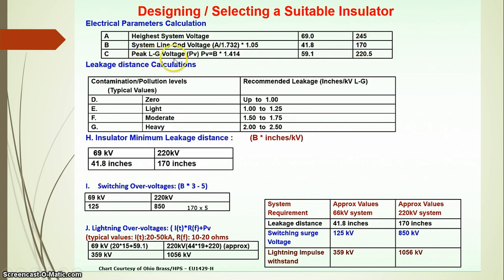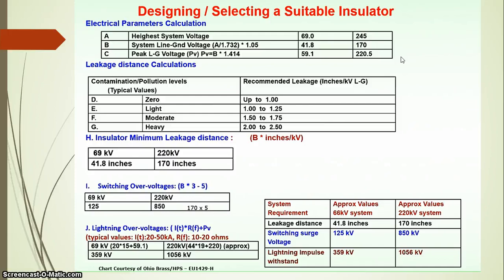The 245 kV is the maximum operating voltage level of the 220 kV system and is an RMS value, not a peak value. The peak value is calculated: 170 kV RMS line-to-ground voltage multiplied by root 2 gives a peak line-to-ground voltage of 220.5 kV. So for a 220 kV system with maximum operating voltage of 245 kV RMS, the peak phase voltage is 220.5 kV.